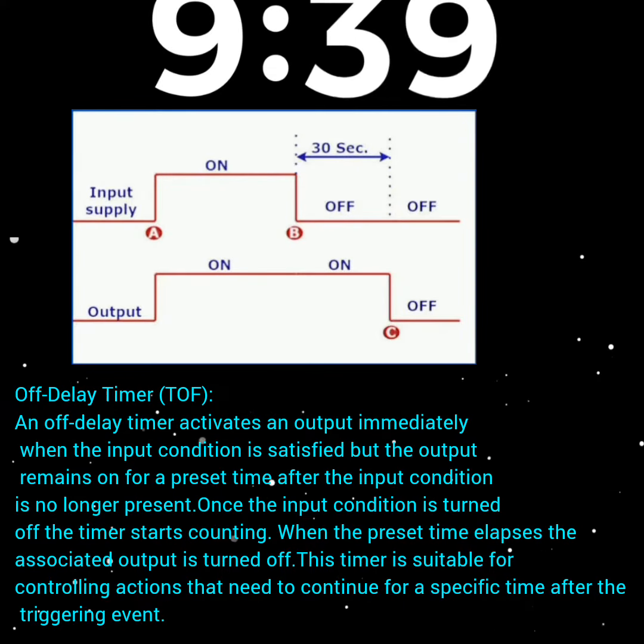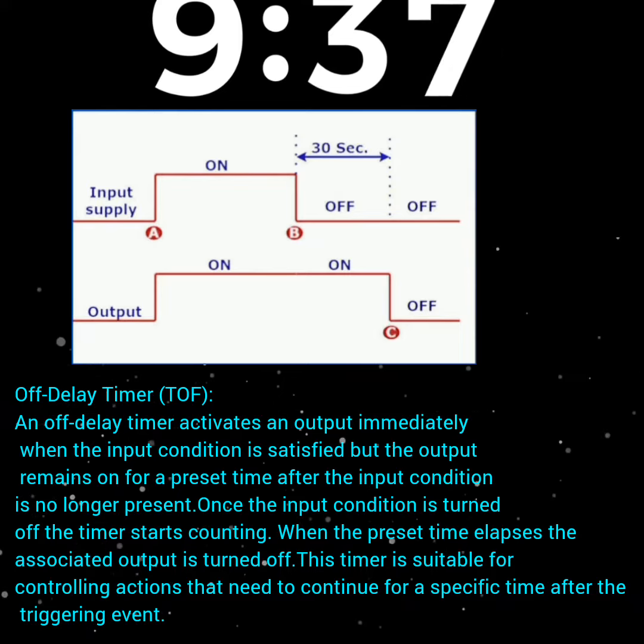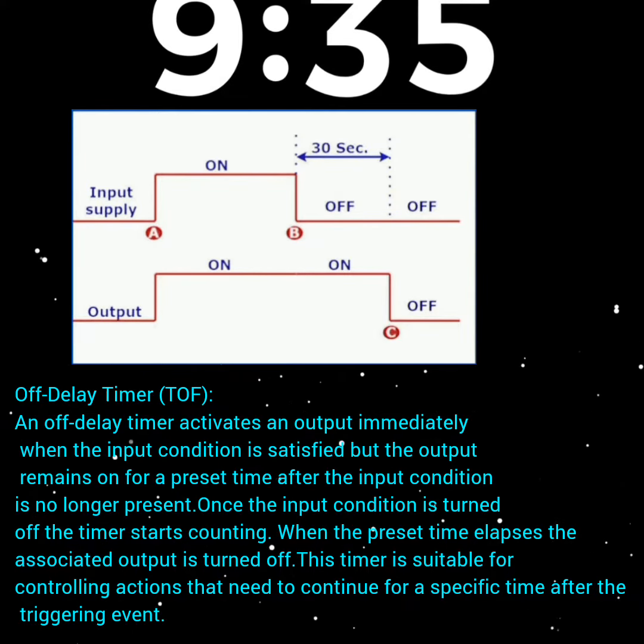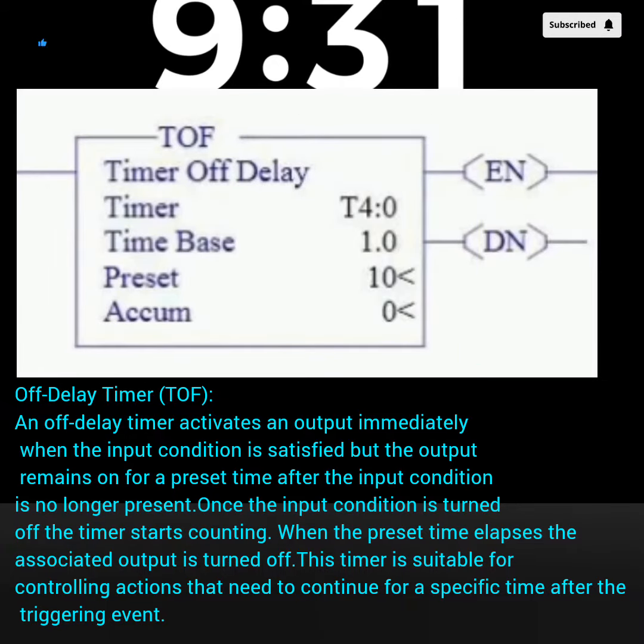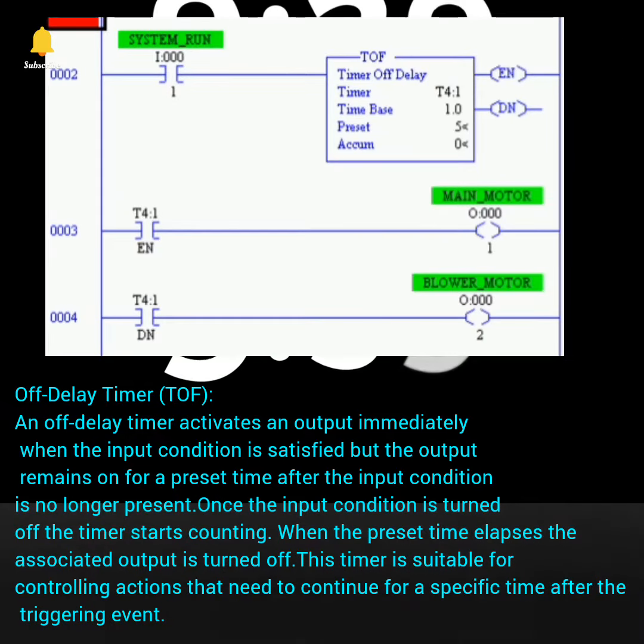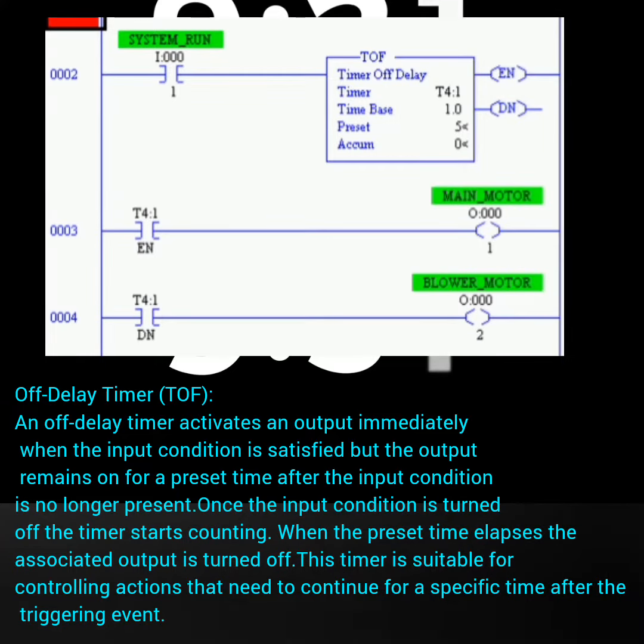2. Off-delay timer, TOF. An off-delay timer activates an output immediately when the input condition is satisfied, but the output remains on for a preset time after the input condition is no longer present. Once the input condition is turned off, the timer starts counting. When the preset time elapses, the associated output is turned off. This timer is suitable for controlling actions that need to continue for a specific time after the triggering event.